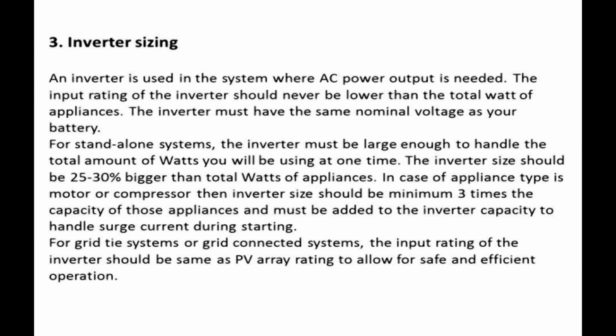Step 3: Inverter sizing. An inverter is used in systems where AC power output is needed. The input rating of the inverter should never be lower than the total watts of appliances. The inverter must have the same nominal voltage as your battery. For standalone systems, the inverter must be large enough to handle the total watts used at one time. The inverter size should be 25–30% bigger than the total watts of appliances. For motor or compressor type appliances, the inverter size should be a minimum of three times the capacity of those appliances, to handle the surge current during starting.